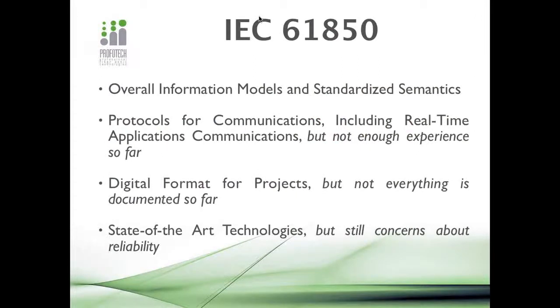Briefly about the standard itself. First of all, it has overall information models and standardized semantics for functions, for devices, and so on. This is actually one of the crucial points and one of the biggest advantages of IEC 61850 compared to other communication standards and protocols in power energy.